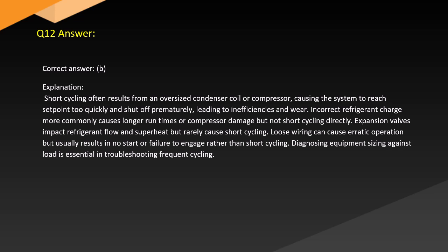Answer. Correct answer. B. Explanation. Short cycling often results from an oversized condenser coil or compressor, causing the system to reach set point too quickly and shut off prematurely, leading to inefficiencies and wear. Incorrect refrigerant charge more commonly causes longer run times or compressor damage, but not short cycling directly. Expansion valves impact refrigerant flow and superheat, but rarely cause short cycling. Loose wiring can cause problems, but usually results in no start or failure to engage rather than short cycling. Diagnosing equipment sizing against load is essential in troubleshooting frequent cycling.